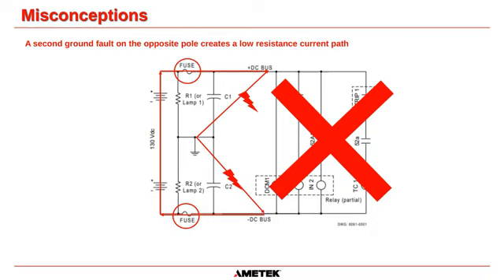Thank you, Andre. Installation monitoring device, and you are absolutely correct. So basically, what Andre is asking is, how does PWM on a UPS affect the voltage sensing on an installation monitoring device? And in truth, it's not just PWM. It can be the switching of the rectifier as well. Because the Bender and the installation monitoring device that sends a signal to monitor the ground fault relies on the same signal coming back identical to what it is expecting, any other common mode noise that is on that circuit can affect it.